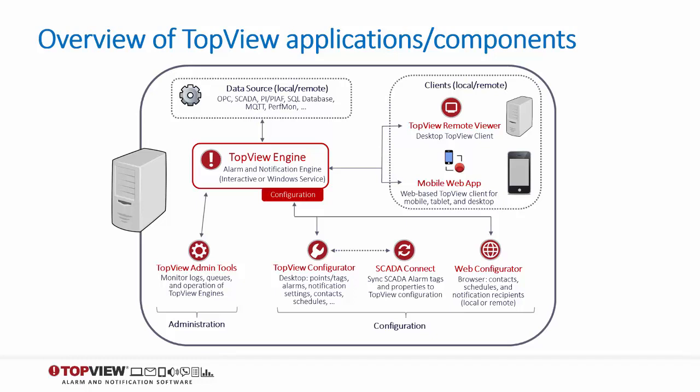There are two primary applications for configuration of the Top View engines. The Top View Configurator is the primary configuration tool. This desktop application allows the user to configure the tasks for each instance of the Top View engine, including the points or tags to monitor, alarm limits, and notification settings. The Web Configurator is a web-based version of the desktop configurator and can run local or remote to the Top View machine.